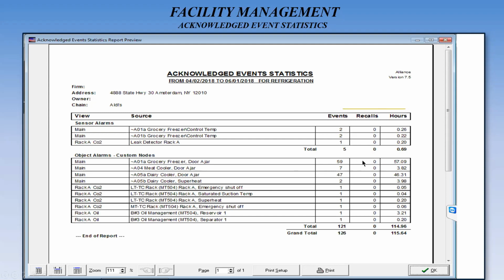The next thing is called the recall. What do we mean by that? If the store manager or the contractor acknowledges the alarm to make it go away, well, we just don't want somebody to put a Band-Aid on it and walk away. So let's say it's prime cut meat and the temperature's too high, and all that technician does is alarm silence, but doesn't take care of the problem.